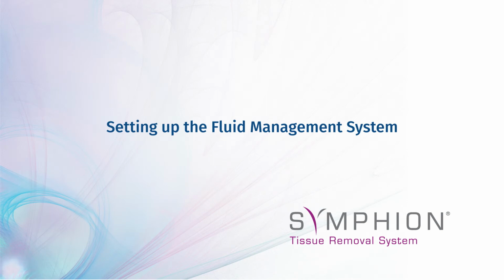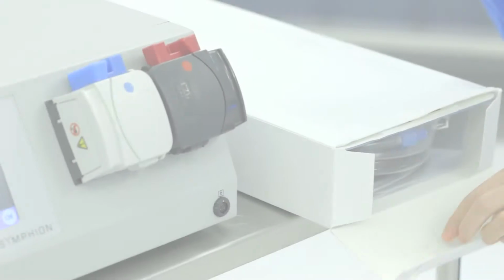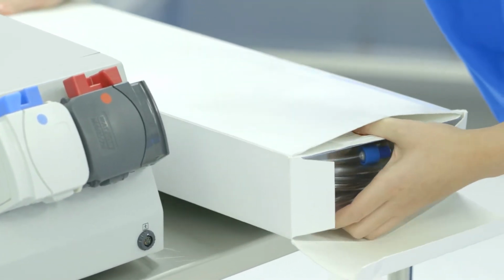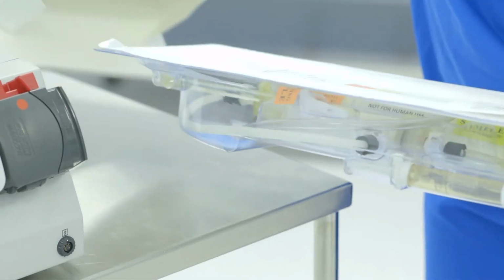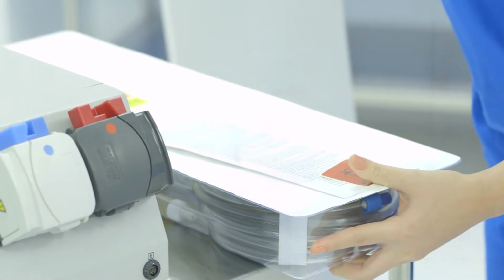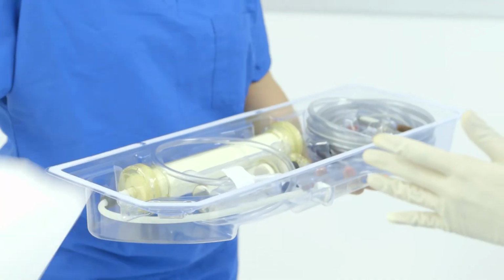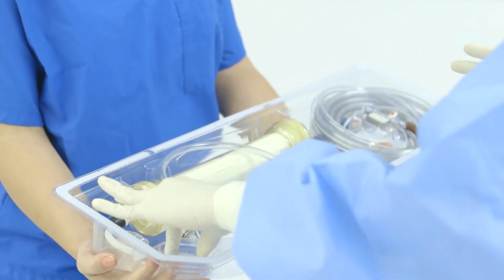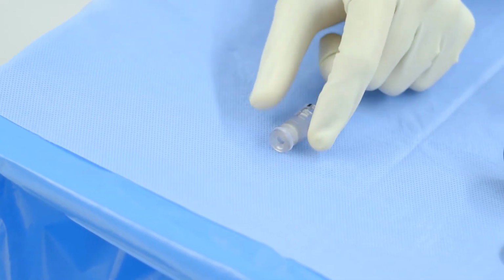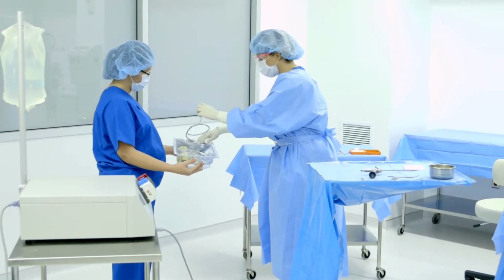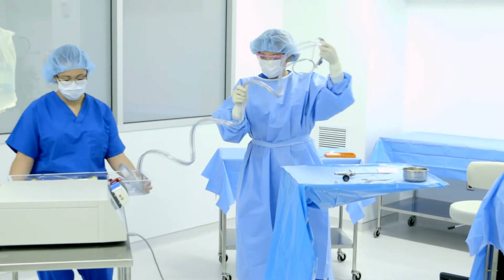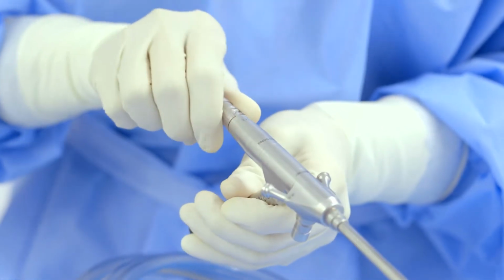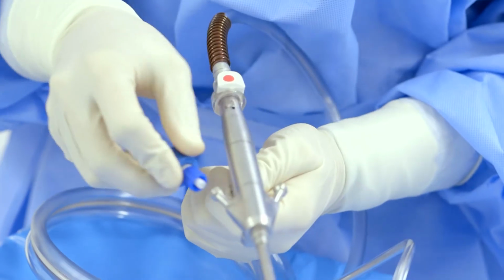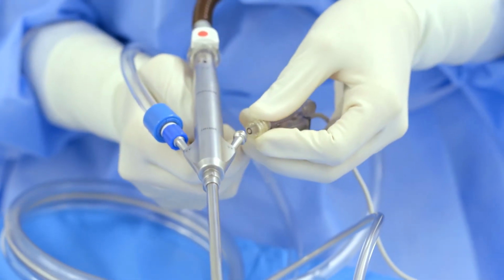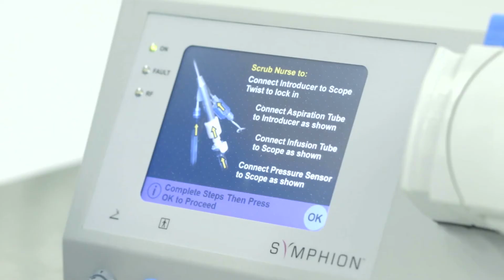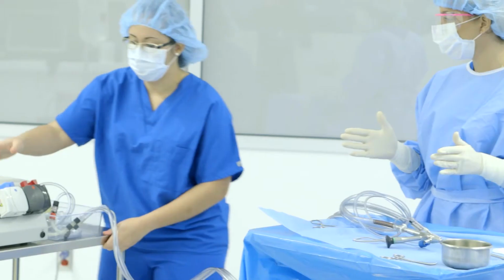Setting up the fluid management system. The closed-loop fluid management system delivers a continuous flow of sterile saline, helping to ensure continuous visualization and minimizing the risk of fluid overload. Following sterile practice, remove the introducer and the sterile connections of the tubing set and the pressure sensor from the fluid management tray, leaving the rest of the components inside. Place the fluid management tray next to the controller. Connect the introducer, the aspiration and infusion tube, and the pressure sensor to the endoscope. Press OK on the controller screen to proceed.